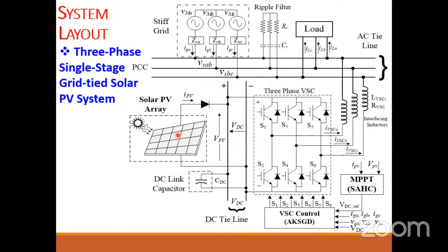So if 700 is the MPP voltage, then what will be the voltage of the panel, meaning VOC, the open circuit voltage of this panel? Definitely when you calculate the open circuit voltage of this panel, it will become around 800 or sometimes 850 volts. So 850 volts open circuit voltage, right, of this panel. Then only will you get the 700 volt MPP voltage, the operating voltage of this panel. So when you select the switches here, you will not select the switch for the 700 rating. You will select the switch for 850 or 900 volts, because at switch equal to 0, when this panel is attached on the DC link, that open circuit voltage will appear on the switch during the operation, right?